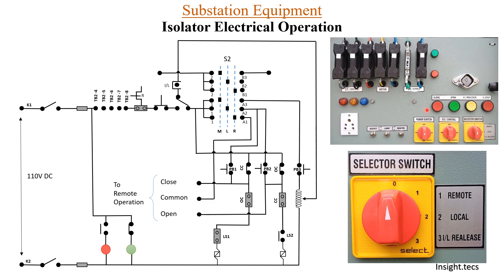Local electrical operation is done using two push buttons — PB1 (close) and PB2 (open). If you want to close the isolator electrically, press PB1 (close push button). The DC moves to the CC contact. Also provided is an NC contact from the OC contactor to confirm the isolator is open before closing. Conversely, if you want to open the isolator, the NC contact of the CC contactor is used.